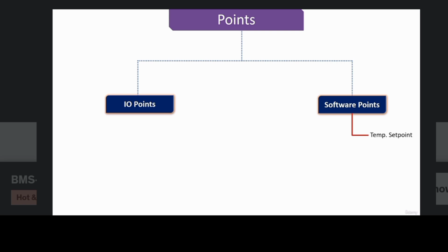An example of a software point is a temperature set point. This temperature set point is created inside the software to control the cooling or heating of an AHU or FCU or VAV. This temperature set point can be changed by the BMS operator from the workstation as per cooling or heating requirements from the occupants.